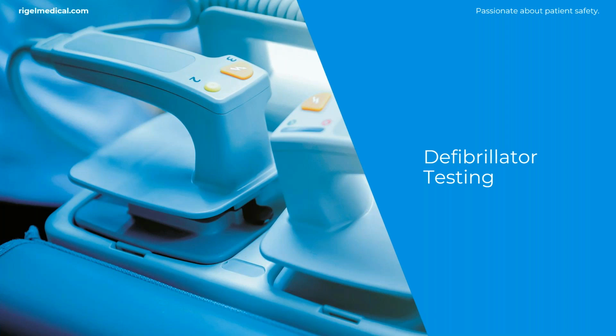Some AED manufacturers will say you just need to do a self-test, and that is sufficient. However, it's not really an external standard. An AED is relying on itself to be safe, which is fine. If the OEM specify that, it's not necessarily a huge issue, but not having an external standard to test is something that a lot of hospitals don't agree with, and they are still carrying out performance tests to make sure they're still working. And there are ways to circumvent some of those issues, like draining the battery during a test, and also using pads that can't be reused.